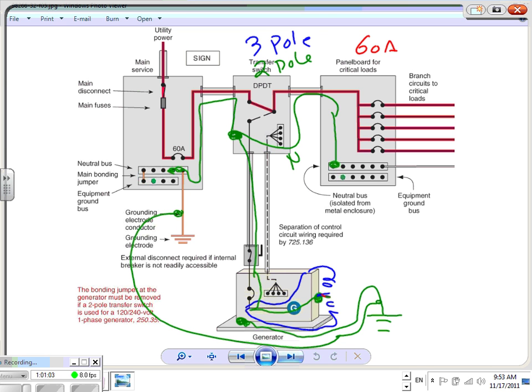Any questions, my friend? If you guys understand this, when we move into generators next quarter, which we're going to be sizing for the two projects that are coming, it will be very easy for you to understand. Can I run this as a separately derived system? Yes, bring it on. Can I run it as a non-separately derived system? Yes. What's the difference? Are you going to bond the neutral at the generator or not? That's the difference. And if you bond the neutral at the generator, then you have to have a three-pole switch here, because you're going to switch the neutral.